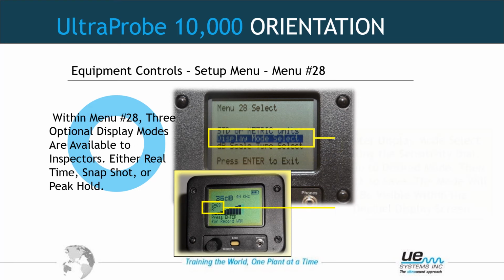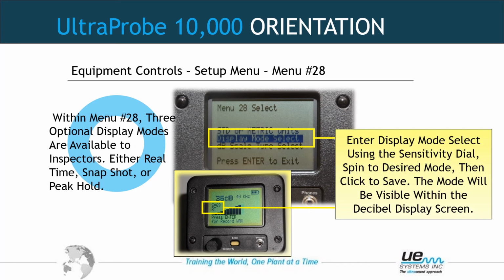The next menu item, menu number 28, is display mode select. Shown here on the bottom picture, you can see that the unit is in a real-time RT mode. This will either be RT, PK for peak hold, or SS for snapshot. Typically, everything we teach today is used in a real-time mode. So keep this in a real-time mode.